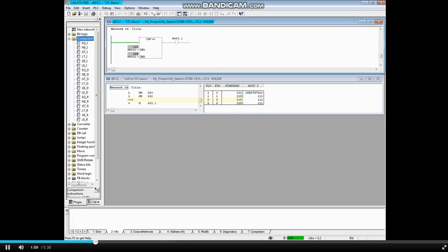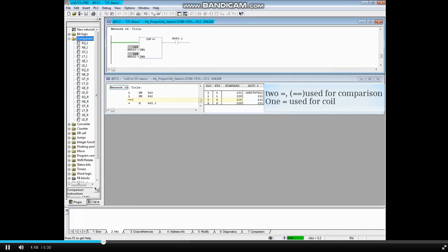The command equals-equals as integers compares accumulator 2 to accumulator 1. The back-to-back equals marks tell the CPU that a comparison is being made, whereas a single equals mark tells the CPU a coil is being written to.